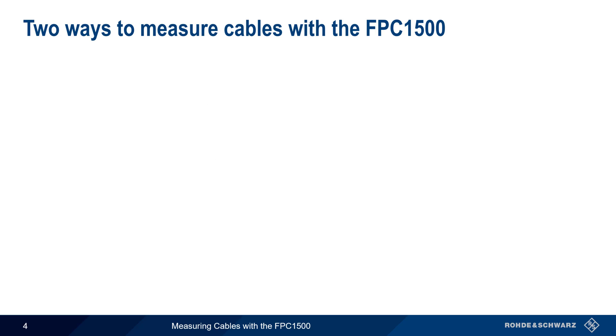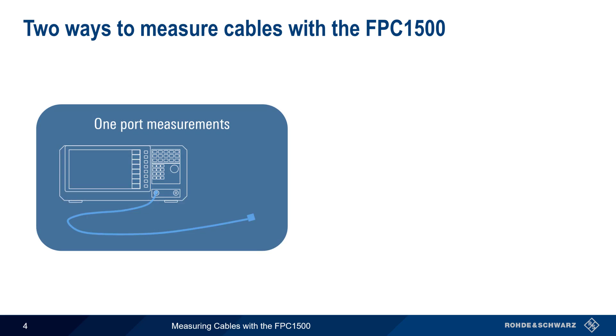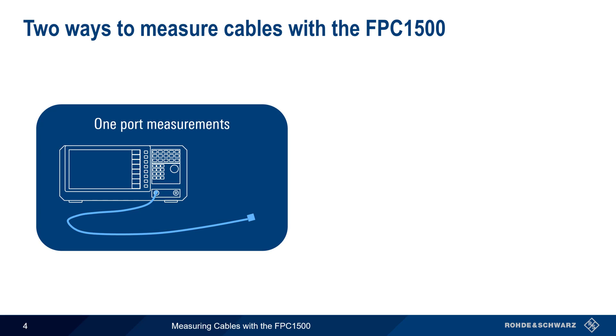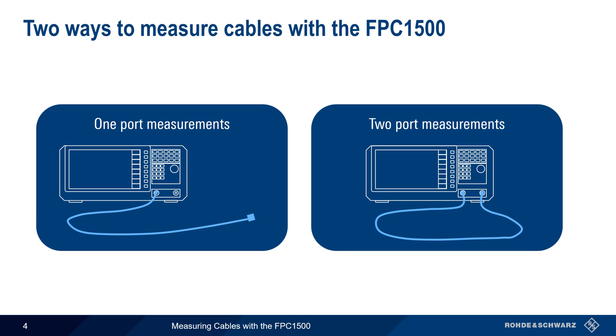There are two ways to measure cables with the VNA mode of the FPC-1500. The first is so-called one-port cable measurements, in which only one end of the cable is connected to the FPC. The other method is two-port measurements, in which both ends of the cable are connected to the instrument. We'll cover both of these methods in this presentation, starting with one-port measurements.